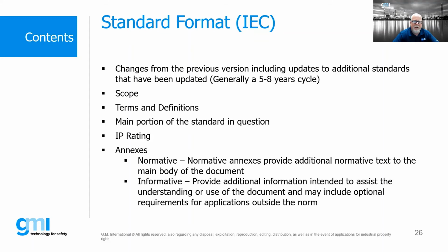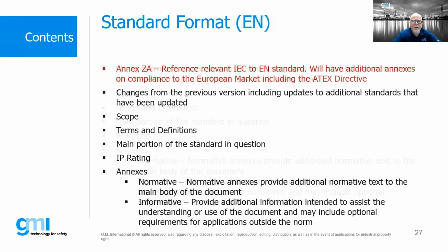It's important to look at the annexes when we're looking at these standards, because sometimes we have questions on them, and usually those questions can be answered by looking in the informative section of the standard. When we look at EN standards, they're basically the same as the IEC standards with the exception of Annex ZA, which references the relevant IEC-to-EN standard, and includes additional annexes on compliance to the European market, including the ATEX directive.